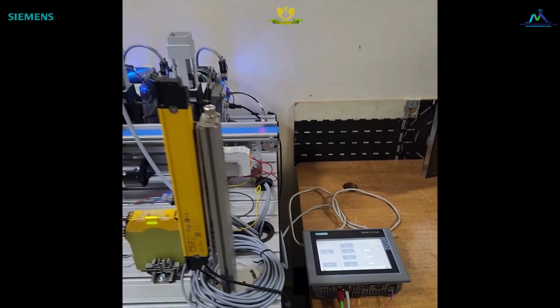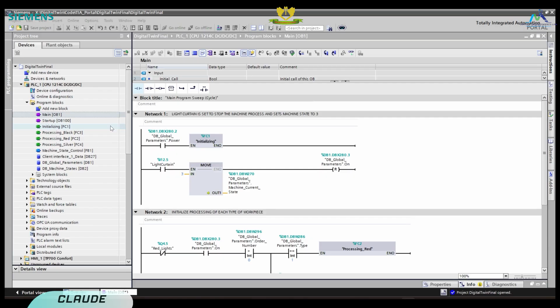For the control logic, the PLC was programmed in TIA Portal using ladder logic, with a modular structure to improve troubleshooting and scalability. The main execution cycle is managed by the main OB1, which continuously scans inputs, executes logic, and updates outputs. During startup, the startup OB100 initializes all variables, resets outputs to a safe state, and ensures the system begins from a known condition.